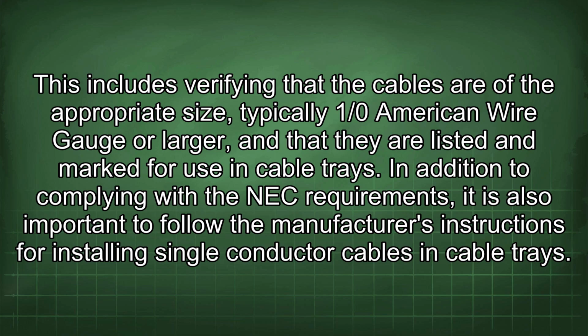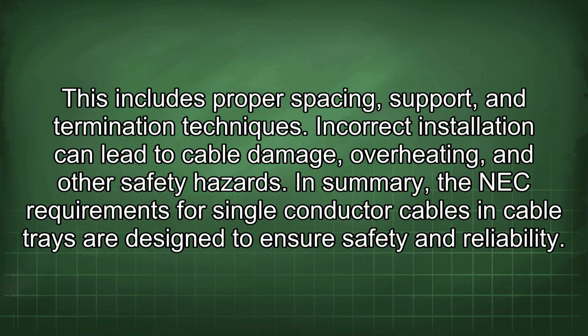In addition to complying with the NEC requirements, it is also important to follow the manufacturer's instructions for installing single conductor cables in cable trays. This includes proper spacing, support, and termination techniques. Incorrect installation can lead to cable damage, overheating, and other safety hazards.